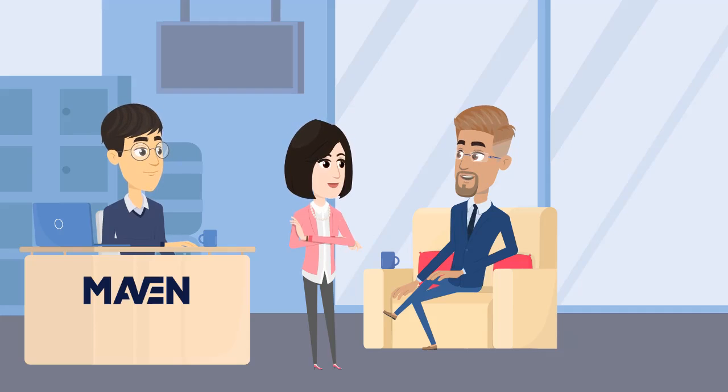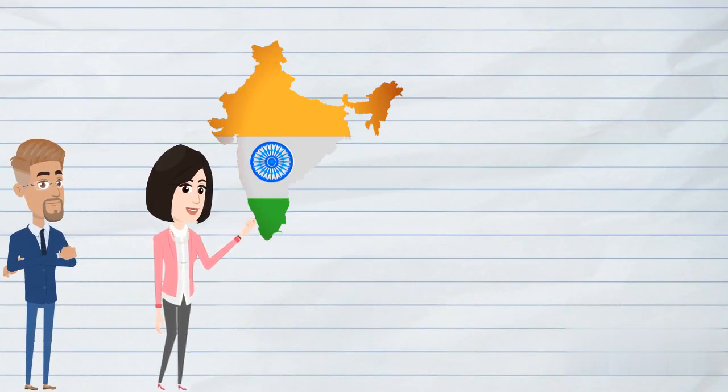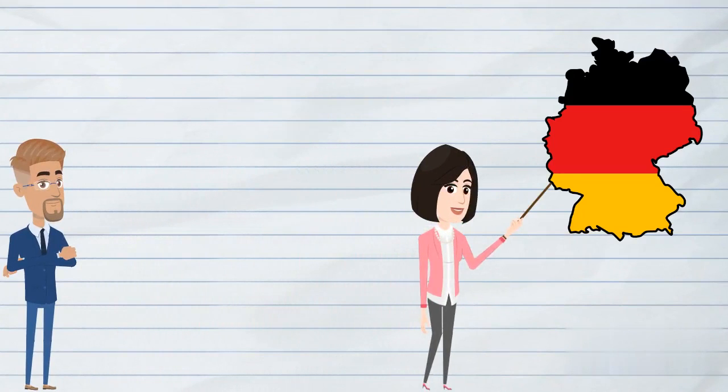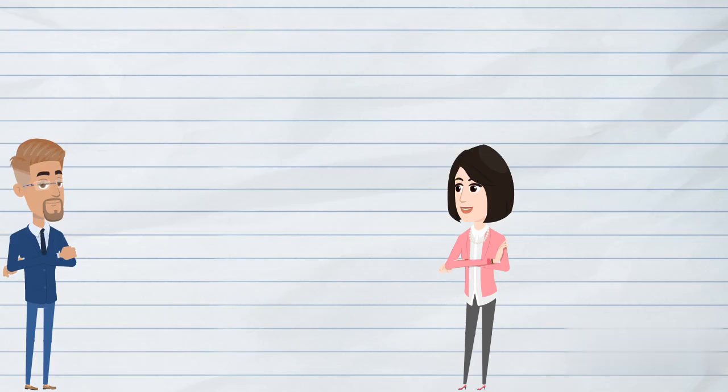Can I be my own EU authorized representative? This question is really interesting, and my answer is yes. For example, your company is based in India and you decide to open an office in Germany. The German office can be your authorized representative. To be honest, this would be the best scenario with only one condition. You need to have a regulatory compliance person at this office. The objective is not only to have a European address but also to perform all the tasks of an authorized representative.